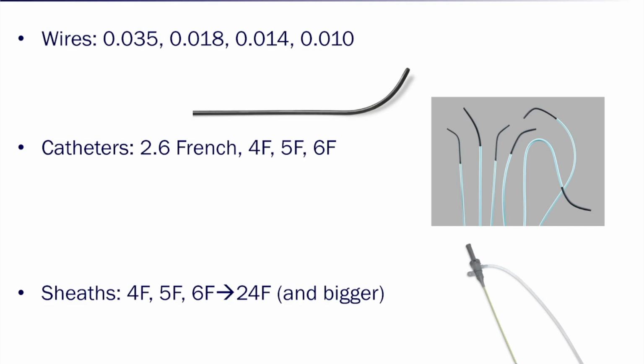Contrarily, a sheath is also measured in French, but it's the inner diameter. And so it's important to keep those things straight when you're trying to put catheters through sheaths and you think, oh, well, this is going to fit this, but it's not quite that simple. An example of this is that a 0.035 inch guide wire won't fit through a 3 French catheter, even though 3 French is over 0.035 inches. You'd think, oh, that'll fit in there great. It turns out it won't fit. And the reason why is because it's actually the outer diameter of the catheter, not the inner diameter of the catheter.